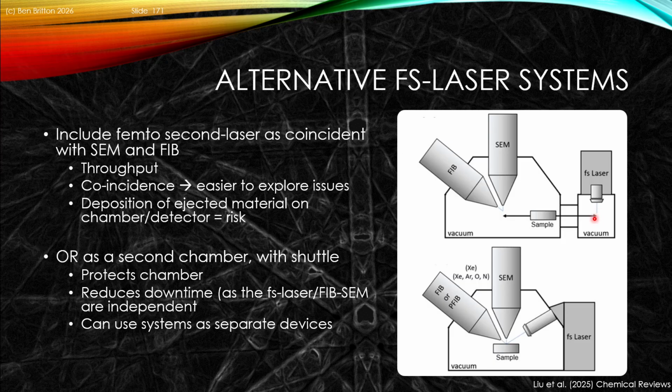The other issue is that because the femtosecond laser is removing so much material, this gets redeposited in the chamber and could cause you lots of redeposition issues that can cause some challenges. And so you might have to worry about protecting detectors or your chamber in these approaches.